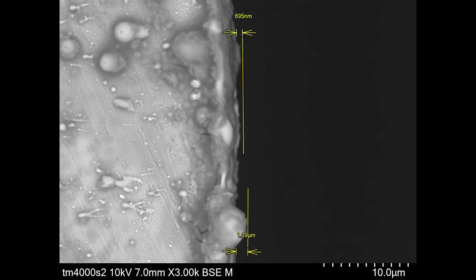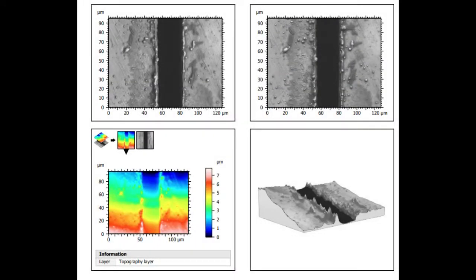Intellectually, I expected what I saw, but just that visceral gut feeling that you see from all of these defects that are along these slit edges. Each of the defects, for example, the spalls, where the little pieces of metal stick up above the slit itself, ablation, where a little piece of the side of the slit exploded off during the cutting process. Each one of those introduces an artifact that affects the resolution of the spectrograph. It really affects the diffraction pattern that comes off of the slit.